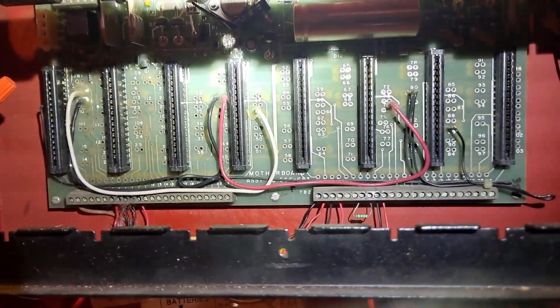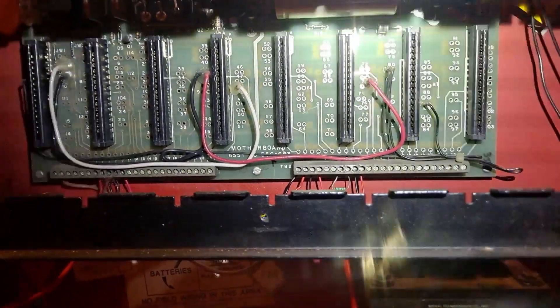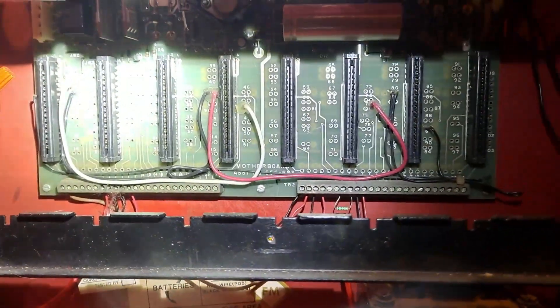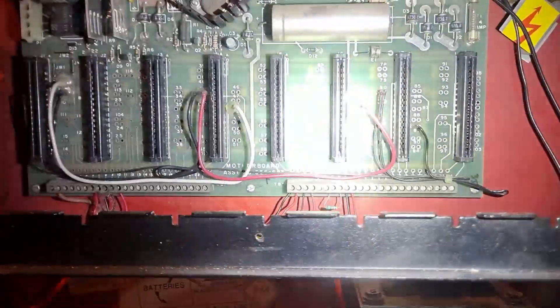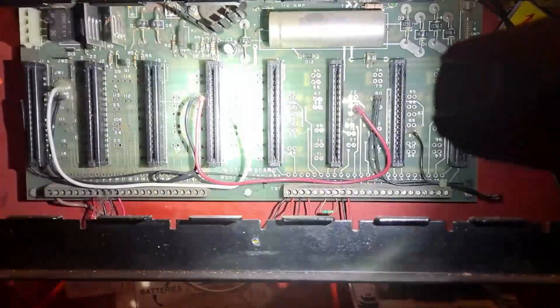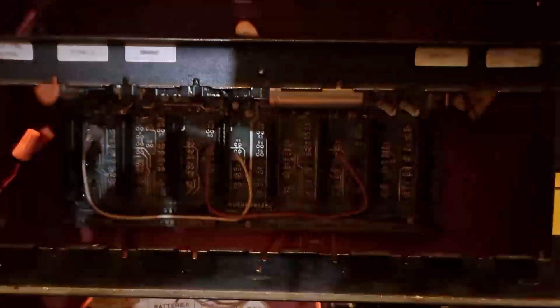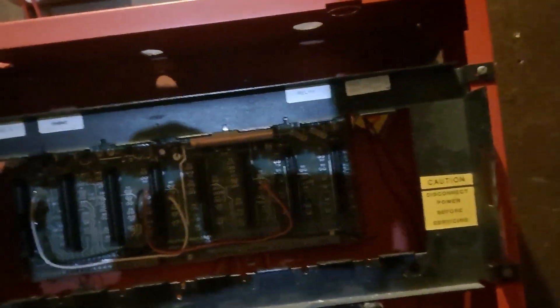It's actually not too hard to figure out once you get the gist of it. Honestly, one of my favorite things about this panel is that besides the control card in the far left, you can just drop in as many signal cards or zone cards as you have card slots on this board, and it just works. It doesn't matter how you do it - you don't have to do any jumpers or anything. Obviously if you're using more advanced cards you'll have to do that, but there isn't too much going on inside this motherboard.